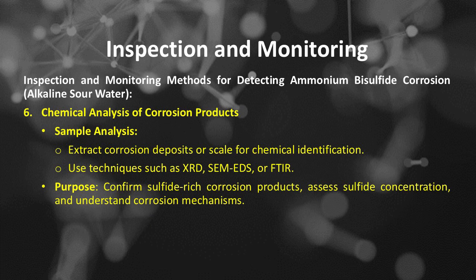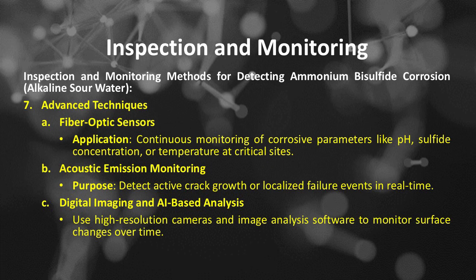Inspection and monitoring methods. Number 6 is chemical analysis of corrosion products. For sample analysis, extract corrosion deposits or scale for chemical identification, using techniques such as XRD, SEM-EDS, or FTIR. The purpose of chemical analysis of corrosion products is to confirm sulfide-rich corrosion products, assess sulfide concentration, and understand corrosion mechanisms.